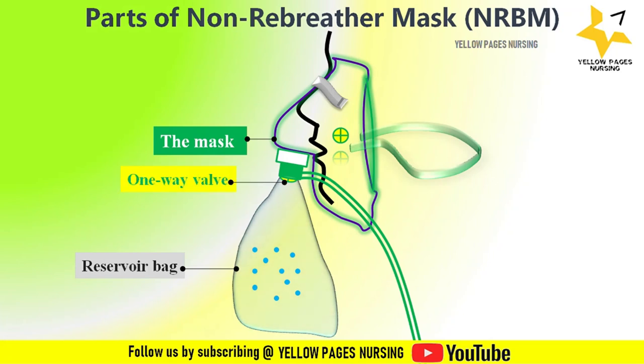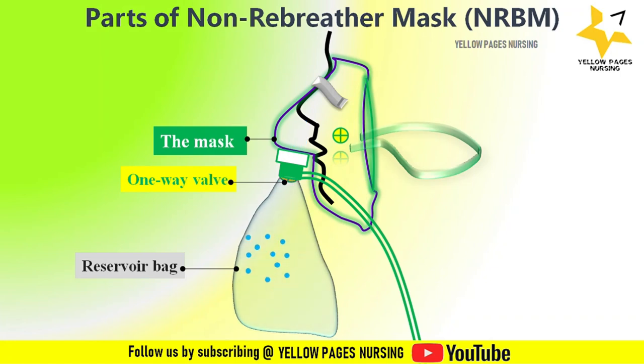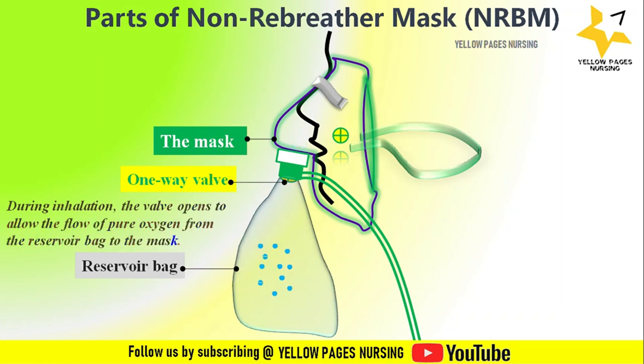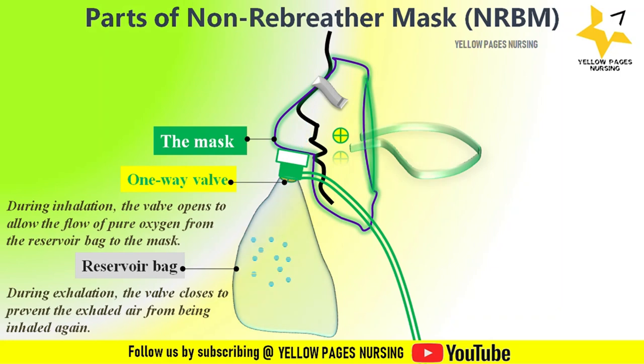The one-way valve between the mask and reservoir bag is also called the inspiratory valve. During inhalation, the valve opens to allow the flow of pure oxygen from the reservoir bag to the mask. During exhalation, the valve closes to prevent the exhaled air from being inhaled again. This ensures that only oxygen-rich air moves from the reservoir bag to the mask during each breath.